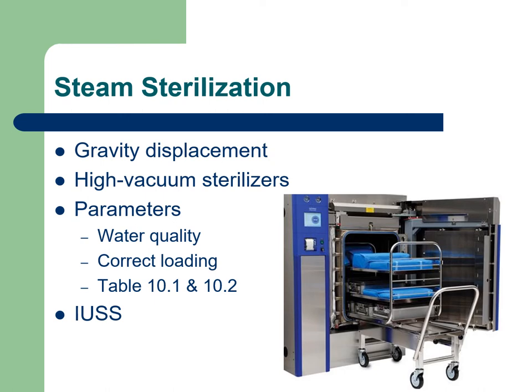Lastly, the immediate use steam sterilizer. We've talked about that before, but we want to make sure we're only using it in an emergency situation, not relying on it to sterilize our instruments regularly. We also want to make sure we're checking all the same things we would check with a standard sterilizer. We do not want to cook implants inside them; the flash sterilizer is not good for sterilizing implants. If we are sterilizing items that have a cannula or lumen, those need to be cooked for a longer time.